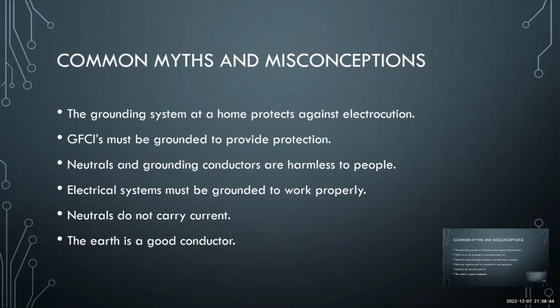Hey, Mike. Those bus bars you were talking about, do they have to be rated by the manufacturer to be used in those panels? Yes, they should be listed for that panel, and they make the ones that come with it. I mean, they're going to come with the panel, but if you have to add an equipment grounding bus, it should be listed for that panel. And they make them. All the major manufacturers, you can buy them mostly at Home Depot and Lowe's. They've got them on the shelf up there usually. Anything that goes in there has to be rated.